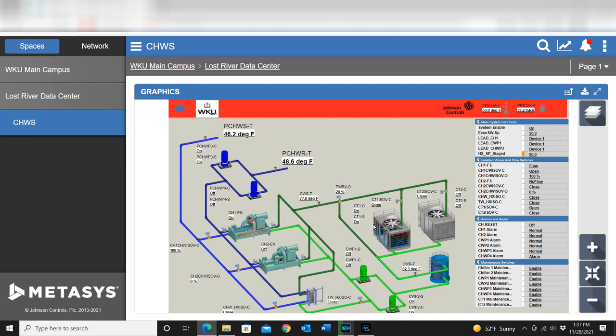What you can do to help minimize that is, just prior to the switch, have your system drop the condenser water temp set point, allowing that water to be cooler in the condenser loop. So when these valves do open up to start flowing water through the heat exchanger, it's actually already gained you a little bit, and it's got colder water going through one side of the heat exchanger than it normally would just as soon as that valve opens. But again, it's not going to eliminate all of that warmer water, but it can help to minimize it. Just be aware of that.